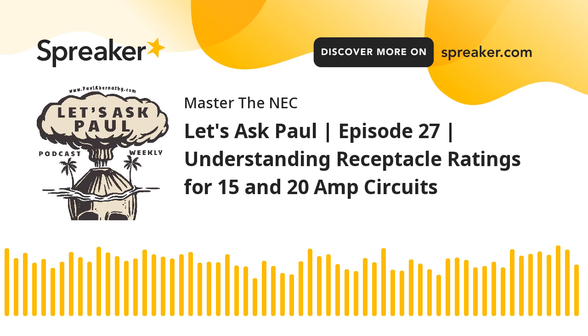Now, can I put a 20 amp rated receptacle on a 15 amp circuit breaker? And the answer is no, you cannot. Okay, so that's the first thing to remember. You cannot use a 20 amp rated duplex receptacle on a 15 amp rated overcurrent protected device. You can't do it. Okay, so 15 amp breaker, 15 amp rated receptacle. 15 amp breaker, you cannot put a 20 amp rated duplex receptacle on it. Okay, makes sense, right? Okay, hang with me now.